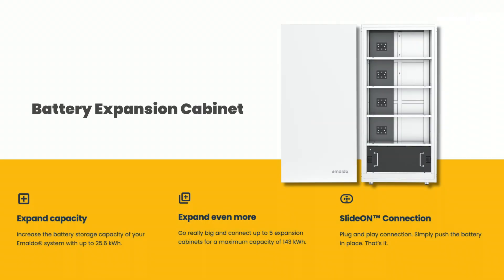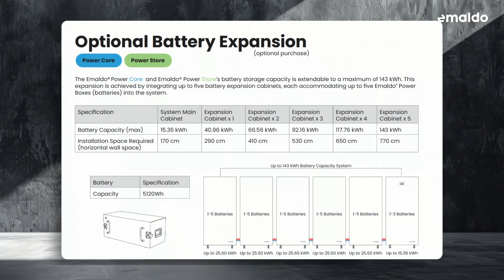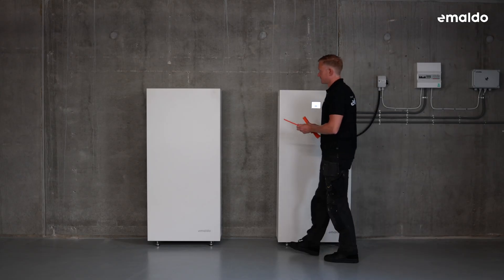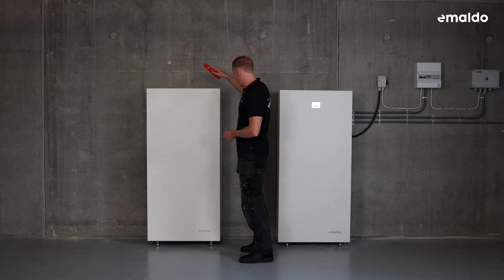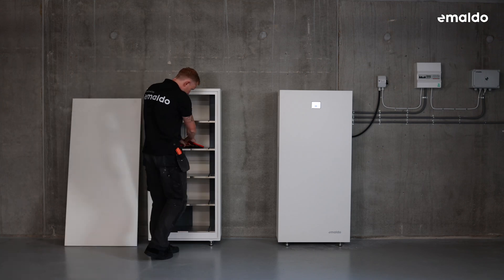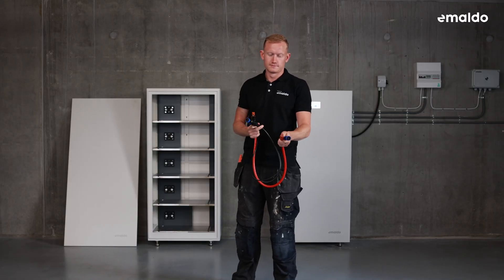Optional battery expansion cabinet: the battery storage capacity of the Emaldo PowerCore and Emaldo PowerStore can be extended up to a maximum of 143 kilowatt hours. This expansion is accomplished by integrating up to five battery expansion cabinets, each capable of housing up to five Emaldo power boxes. Ensure that there is enough free space around the entire system and all Emaldo units are properly leveled. For installations with battery expansion cabinets, it's recommended to position the Emaldo PowerCore or PowerStore on the right side of the designated installation area, making it easier to expand battery cabinets on the left. The one-meter expansion cables are housed in the expansion cabinet.